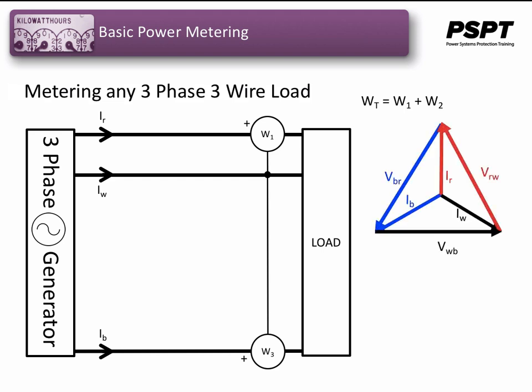Looking at the voltage and current phasors, you see that we are using the red to white and blue to white voltages with the red and blue phase currents. The resultant currents of each element are 120 degrees apart. The resultant voltages of each element are 60 degrees apart. This is the 60 degree, 120 degree configuration that is standard for correct metering arrangements.